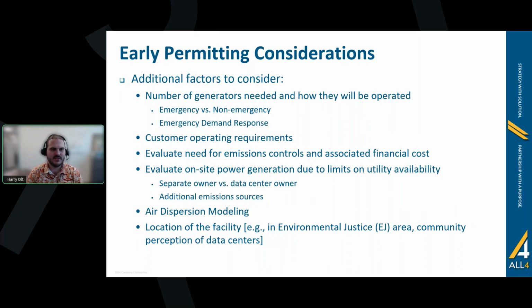Recently, emergency demand response and other similar programs have become a hot button topic, which revolve around an agreement between a data center and the utility provider, where the data center runs its generators in times of high demand or stress on the grid to allow the utility to prevent brownouts. When approached about such programs, it is critical to understand the components, who is initiating and in what circumstances. Then check those against your air permit and the federal rule.